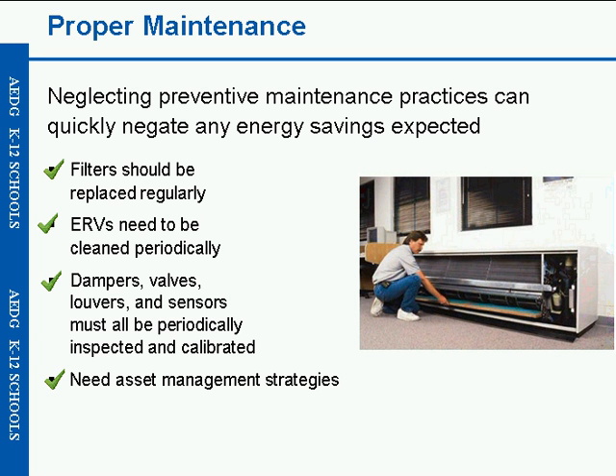We can't stress enough the ability to design systems that are relatively simple and design systems for maintenance. Shanti and I once looked at a school building that had an energy recovery ventilator, and it took us 2 hours to get ourselves into the room and in the right position to remove the filters in this unit. And when we removed those filters, you can anticipate the results, that they were quite dirty and were not terribly effective in helping that equipment operate. And so it's very important to plan for maintenance, have appropriate maintenance documents.